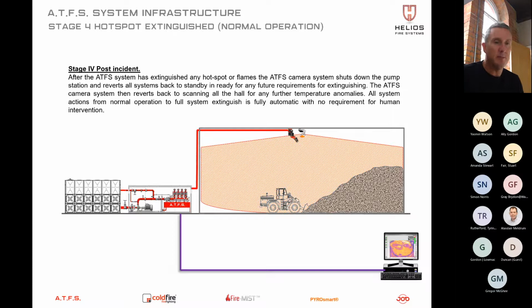What actually happens inside the pump station is we're not allowed to turn this pump off here. So even though the fire's out, we've now closed the valve here in the pump station, but the water is still circulating through the system. We're not allowed by NFPA and LPCB rules to actually switch this fire pump off. That is down to the client to do.